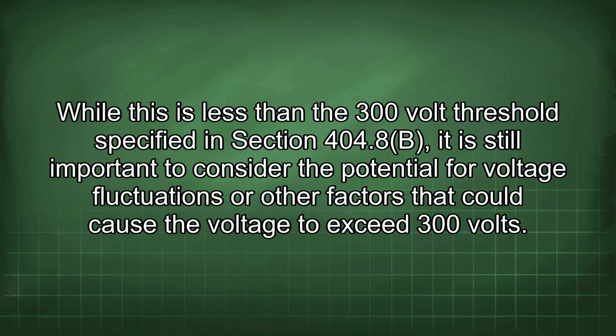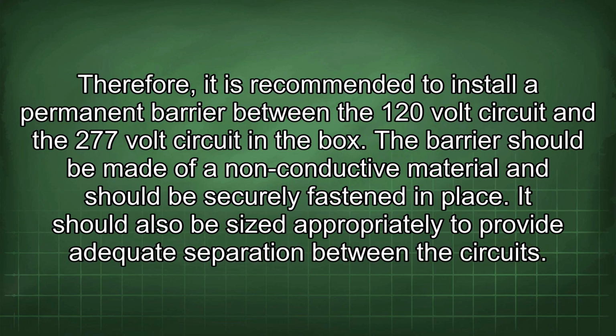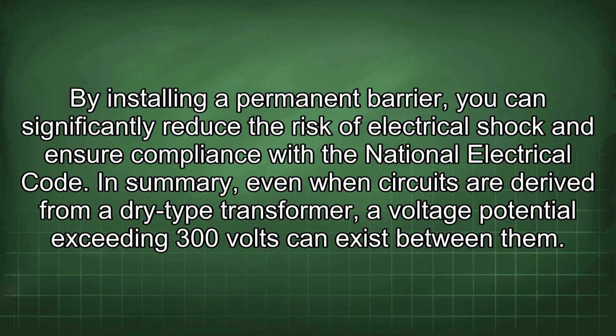While this is less than the 300-volt threshold specified in section 404.8(B), it is still important to consider the potential for voltage fluctuations or other factors that could cause the voltage to exceed 300 volts. Therefore, it is recommended to install a permanent barrier between the 120-volt circuit and the 277-volt circuit in the box. The barrier should be made of a non-conductive material and should be securely fastened in place. It should also be sized appropriately to provide adequate separation between the circuits. By installing a permanent barrier, you can significantly reduce the risk of electrical shock and ensure compliance with the National Electrical Code.